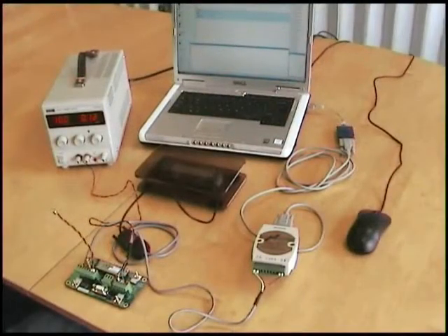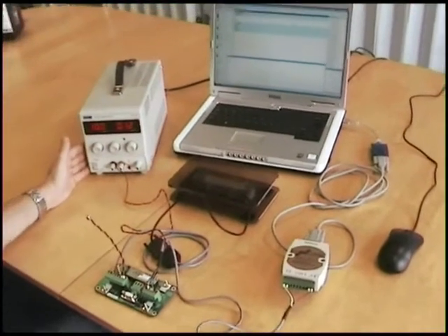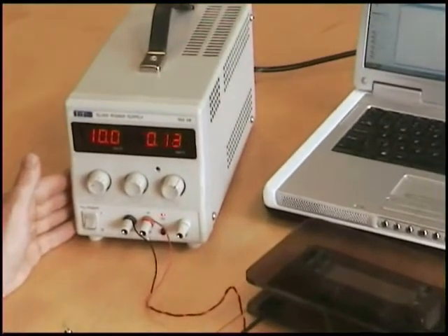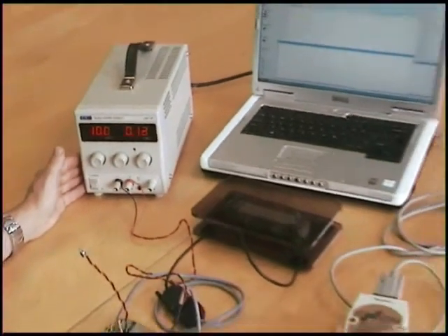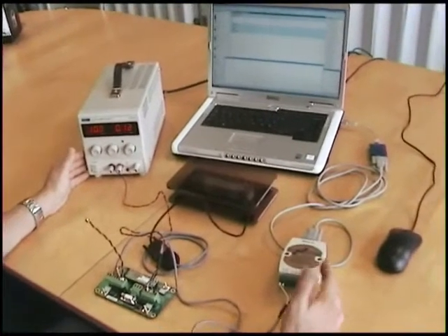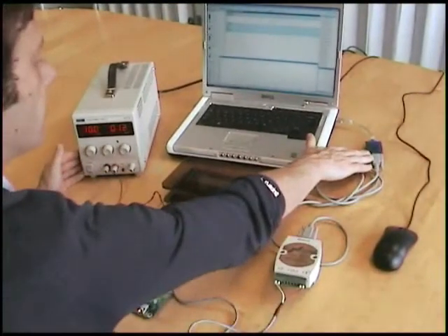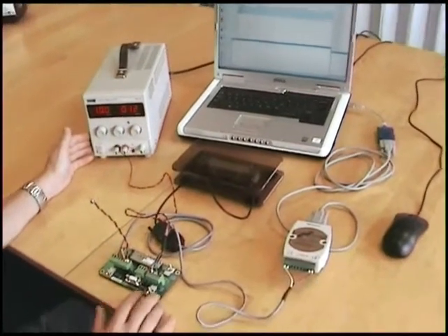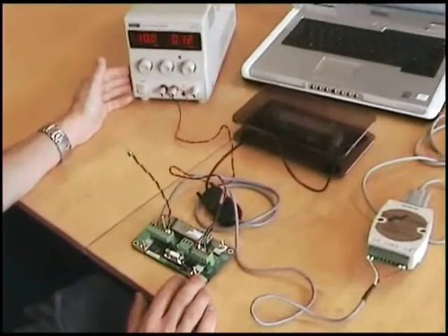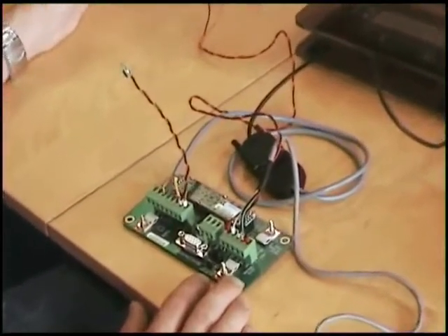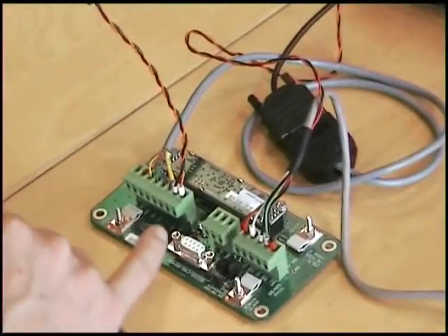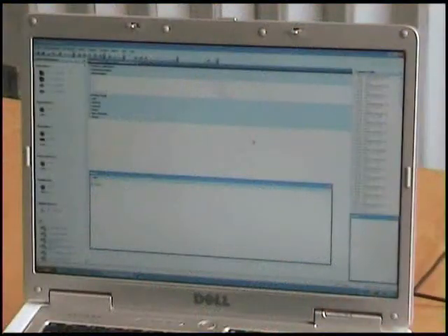Here, the DSJ1 is attached to a power supply, providing 10 to 18 volts. 10 volts is the minimum voltage for the RS232 to 485 converter. The RS232 to 485 converter is attached to the PC via the available COM port, and the RS485 connection comes back to the DSJ1 Junction 1 RS485 COM port. Additionally attached is the temperature sensor and a load cell attached to Junction 2 of the DSJ1. Set up all of your hardware.